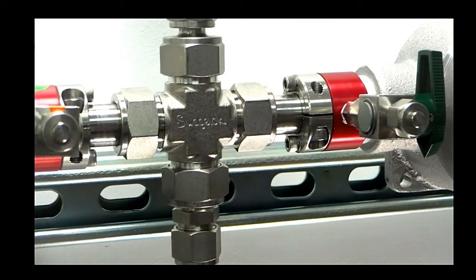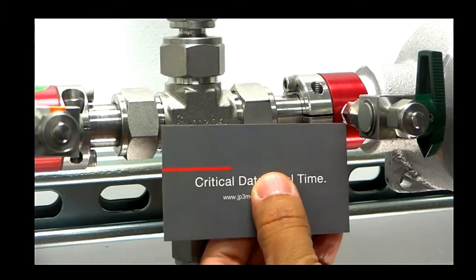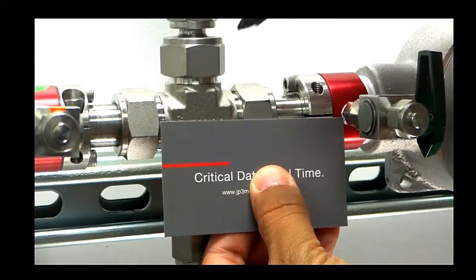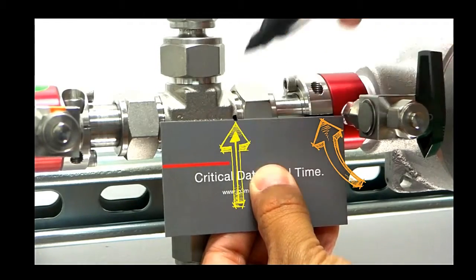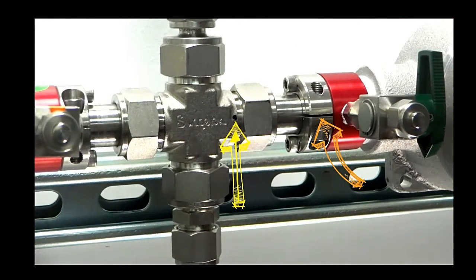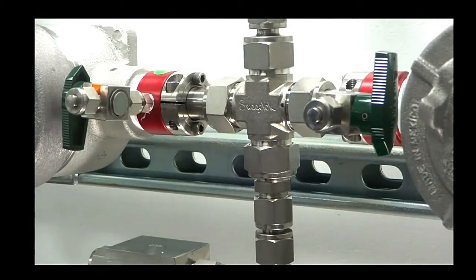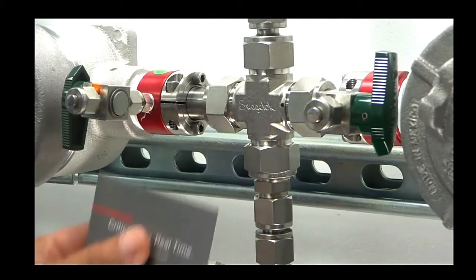Step 2 of the cleaning procedure is to mark reference points. Alignment of the probes is crucial. So using a straight edge, aligned with the cut in the probe, mark an alignment mark on the center cross. This should be done for both sides of the probe set assembly.